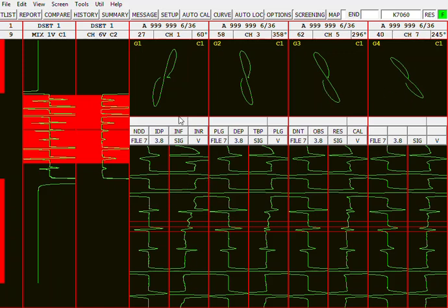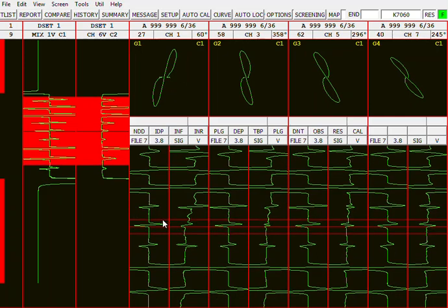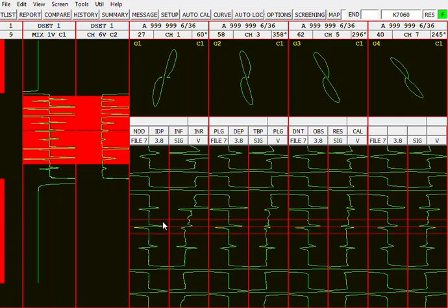But also, I'll just make a statement here that I like to announce a lot, just so you can remember it. Outside diameter flaws will rotate counterclockwise with decreasing test frequency. That's what it does here. This one is rotated a little bit counterclockwise from the higher frequency. This channel is rotated a little bit counterclockwise from the previous higher frequency. So they're rotating counterclockwise with decreasing test frequency.